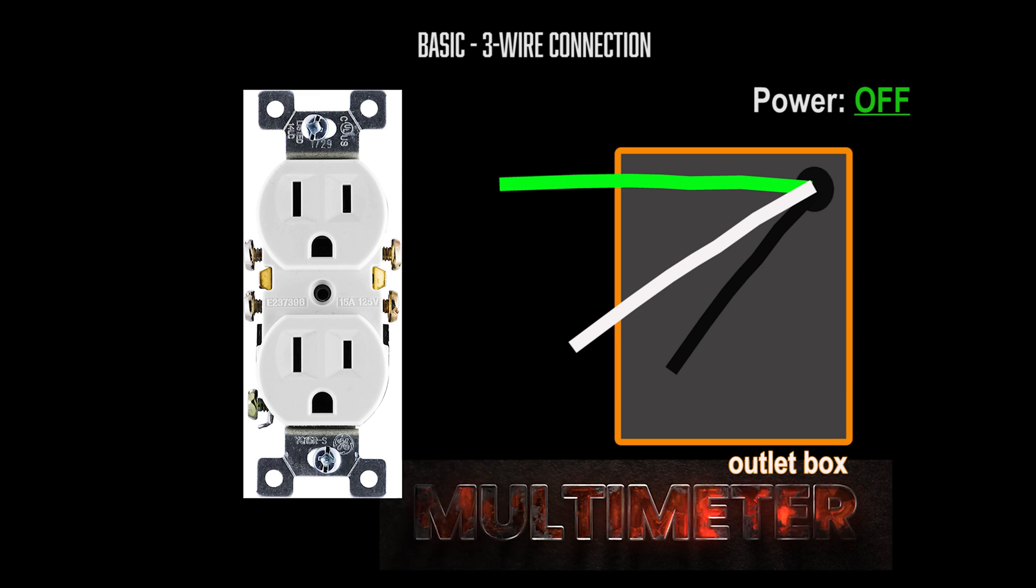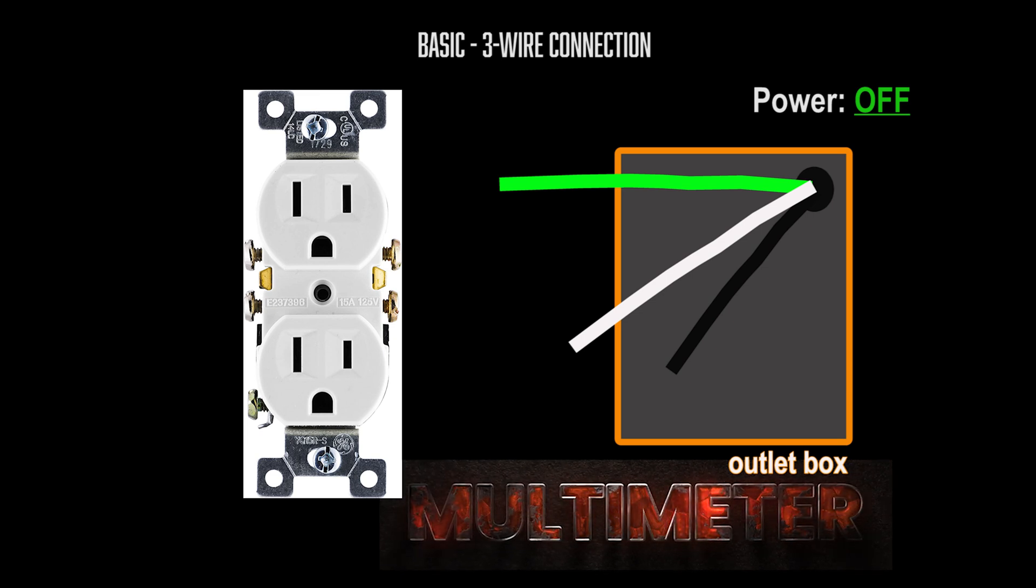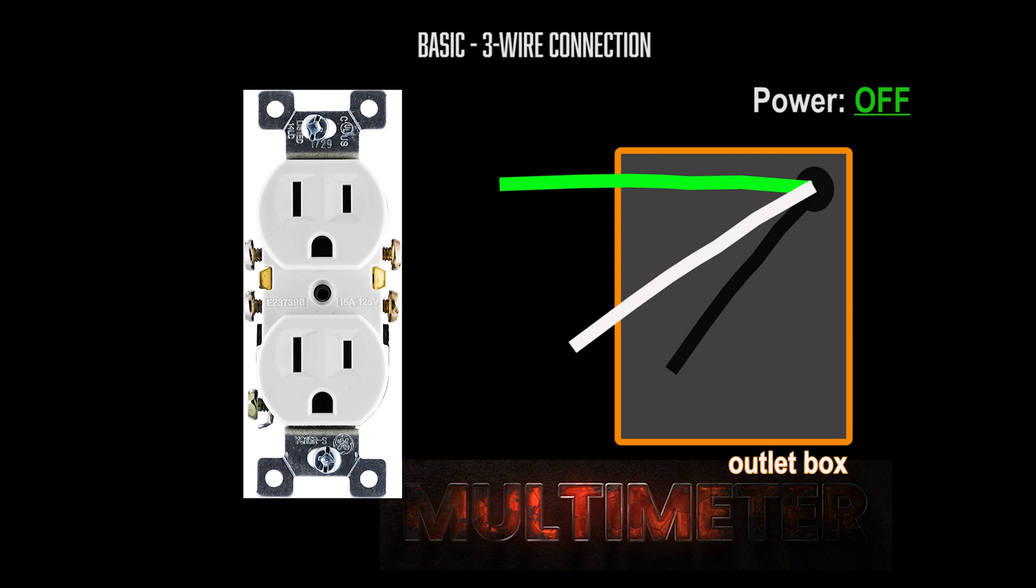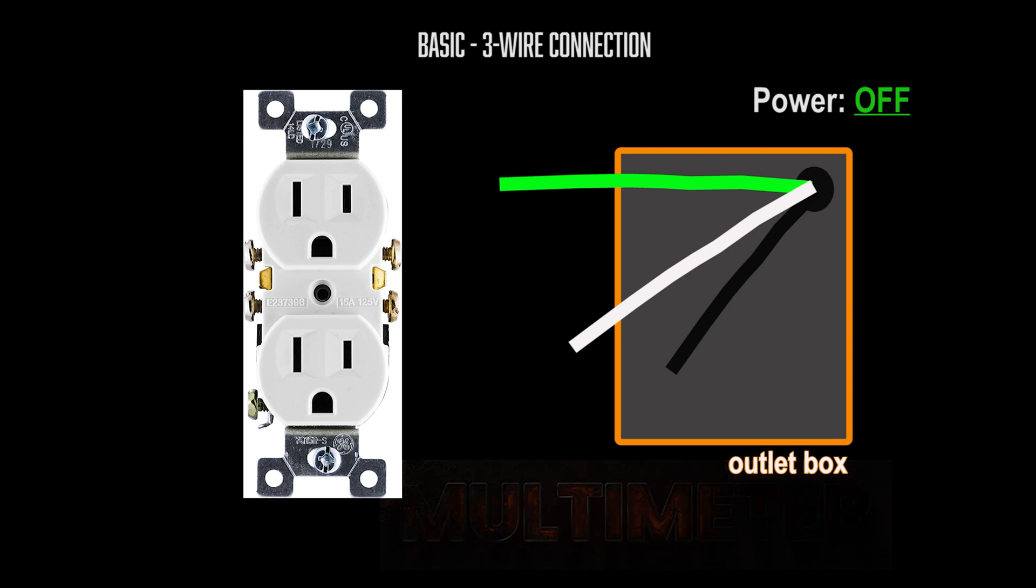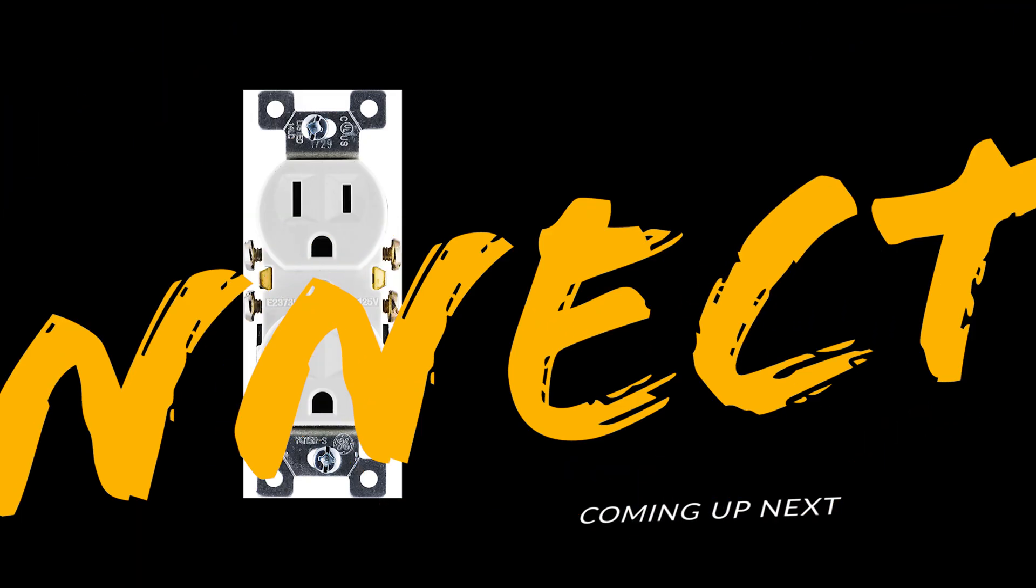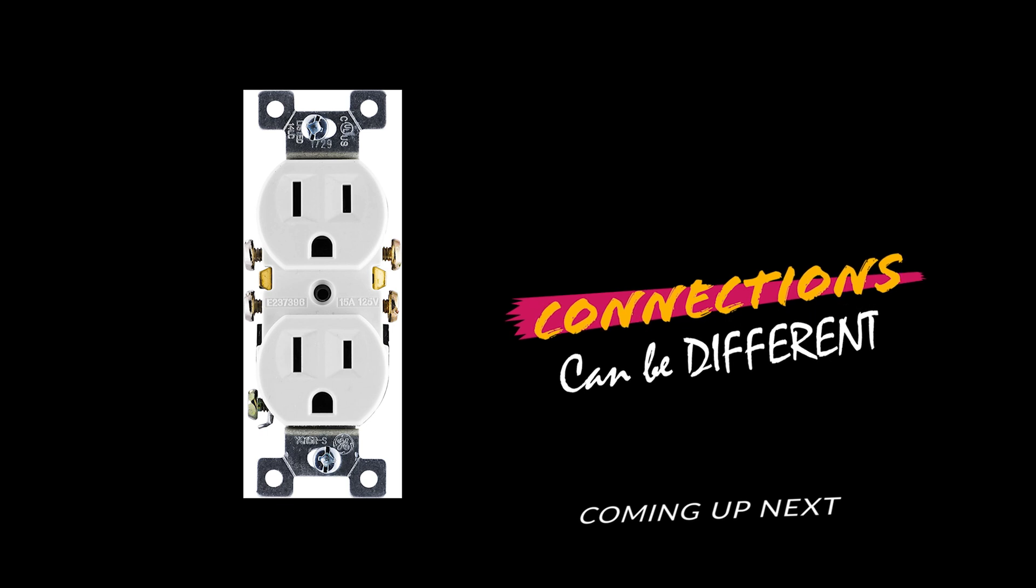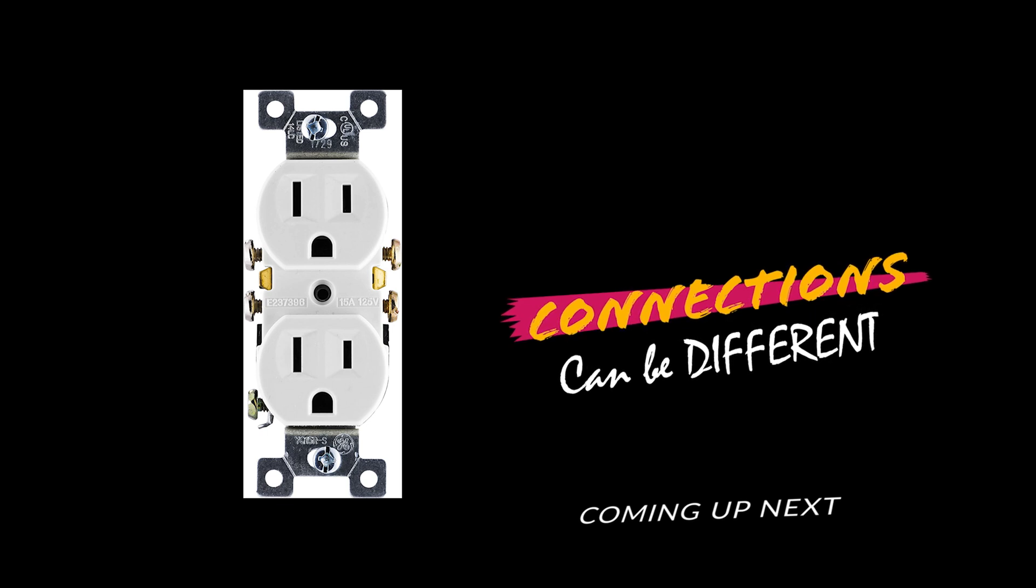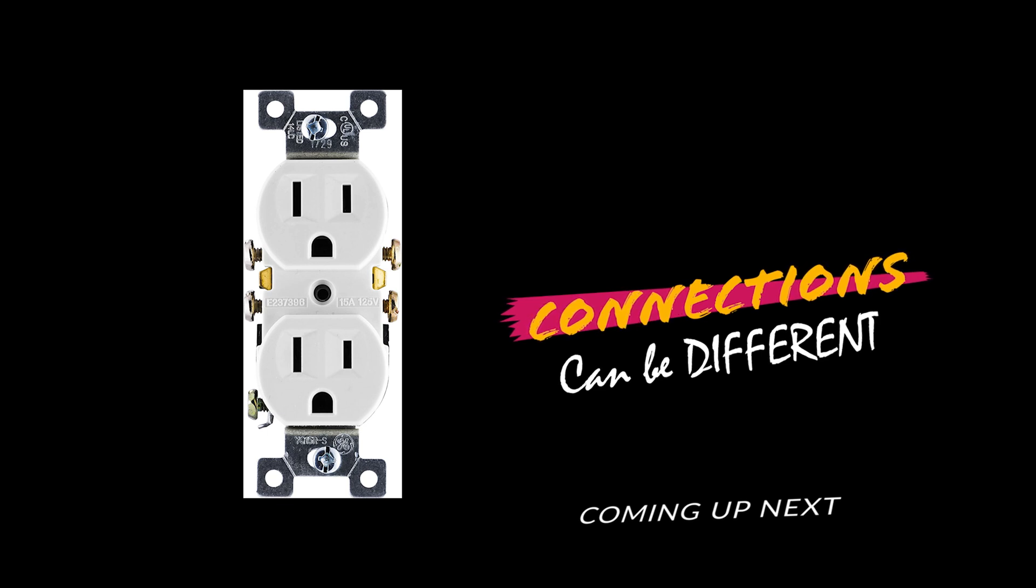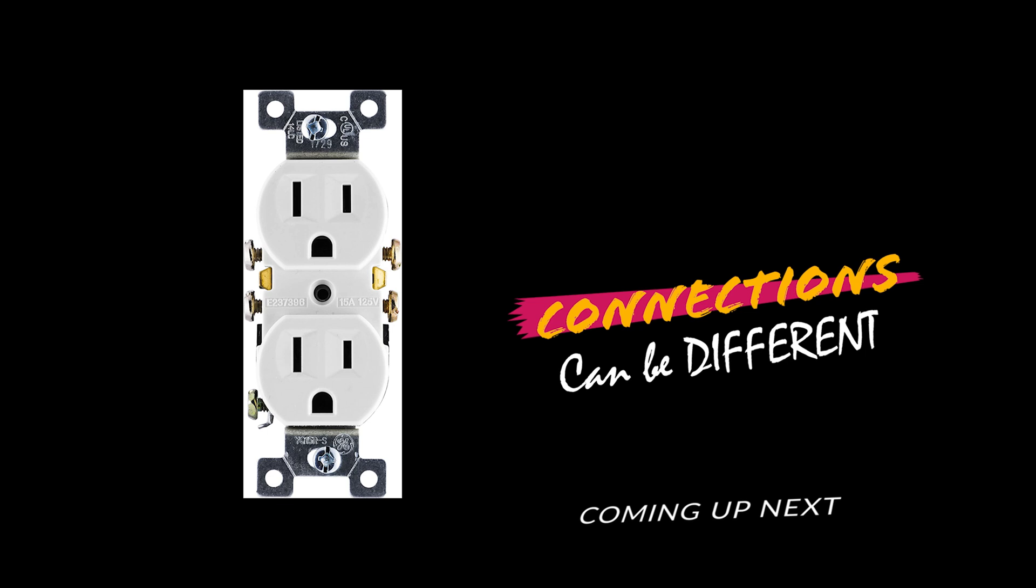This way you're doing the connections for certain and not relying on a proper installation by the last person to assemble this outlet. Plus, not all outlets and light switches have the connections in the same exact places. The connections can be frequently reversed depending on the manufacturer and their particular design, as you will see a little later in my example. So using a multimeter for correct identification is a must.